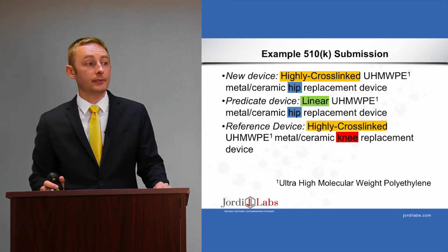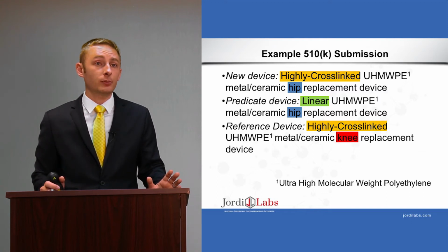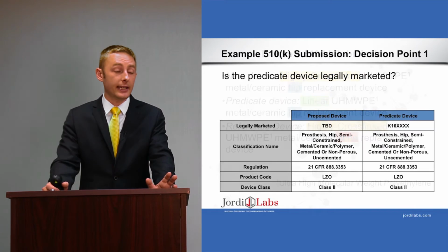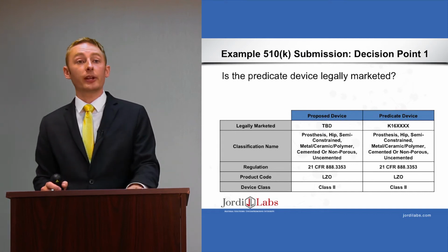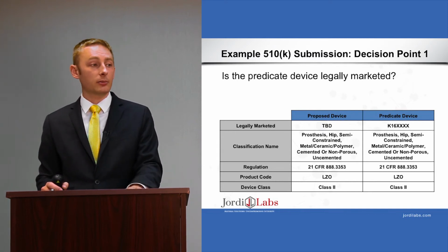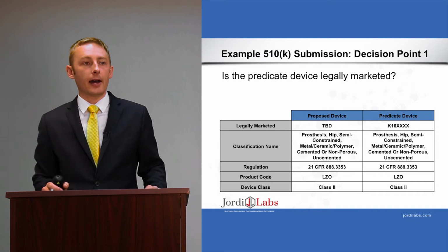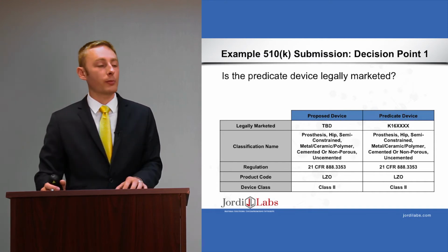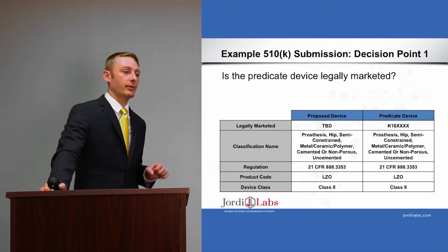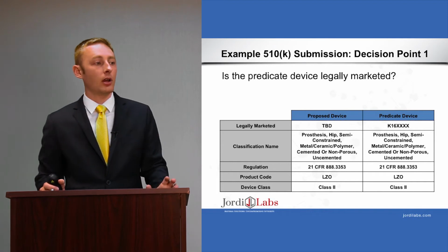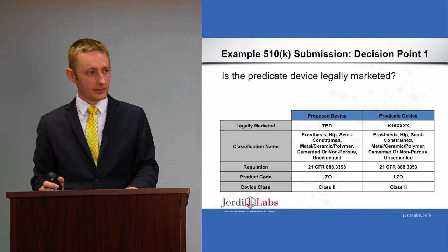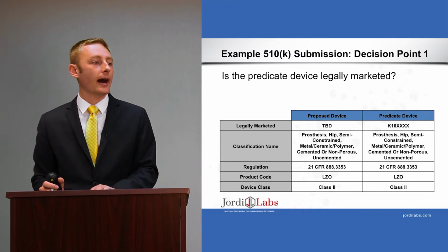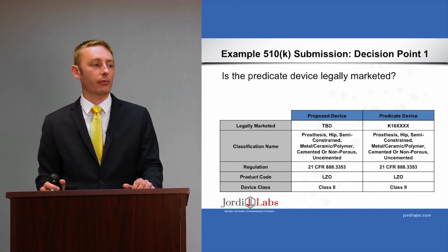And so I guess starting at the decision points that the FDA uses for this: is the predicate device legally marketed? It's going back to basics. Is the device that you're trying to compare this to something that's on the market and ready to go? They prefer this sort of format where you take your new device, your proposed device, and compare that to the predicate device. And so legally marketed, to be determined. Hopefully yes. Actually, probably yes. Predicate device lists the K number for that.